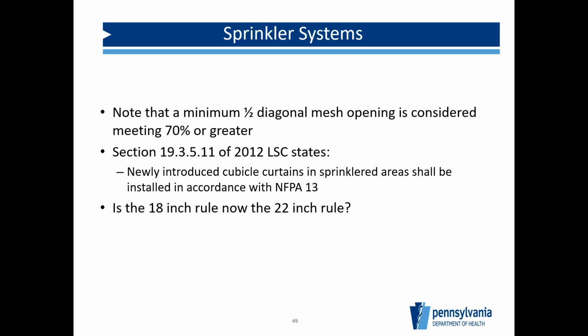So all of our nursing homes are fully sprinklered. So your existing privacy curtains can stay 18 inches, but if you renovate the space, or you decide to buy some new privacy curtains and replace the existing ones, then that's when we want to go to 22 inches of mesh. So if you don't change the unit, don't renovate, don't do new construction, they can stay 18 inches of mesh, you're fine. But as soon as we replace them with new curtains, that's when we need to use the new ones with the 22 inches of mesh at the top. Or you could drop your curtains 22 inches down from the ceiling.